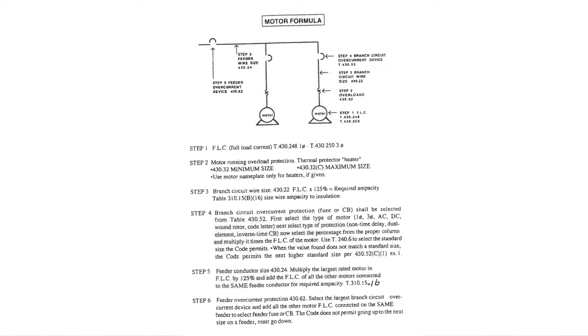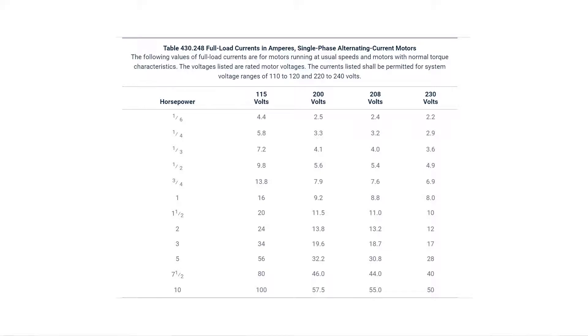These tables are just a quick reference. Now let's look at our 6-step motor formula. Let's look at step number 1. Step number 1 says full-load current, and it tells you the tables we're dealing with is table 430.248 for single-phase, 430.250 for three-phase. Now to understand those tables, let's look at that 430.248. Let's read through the title block and then the actual information. It says full-load currents in amps, single-phase, alternating current motors. The following values of full-load current are for motors running at usual speeds and motors with normal torque characteristics. The voltages listed are rated motor voltages. The currents listed shall be permitted for system voltage ranges of 110 to 120. See in the middle there, it's got 115 on the table. And then 220 to 240. See in the middle there, you've got 230.